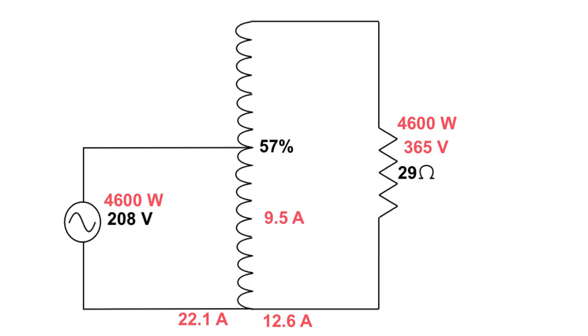And there you have it. We've worked out everything. Again, kind of easy, kind of fun. We get the voltage, we divide it by the percentage to get the voltage at the load. We take the voltage at the load, divide it by the load to get the current. We take the voltage and the current to get the power. Power in is power out. So we take this power over to this side. This side divided by 208 gives us this current. And then this current minus this current gives us the current across the common winding.